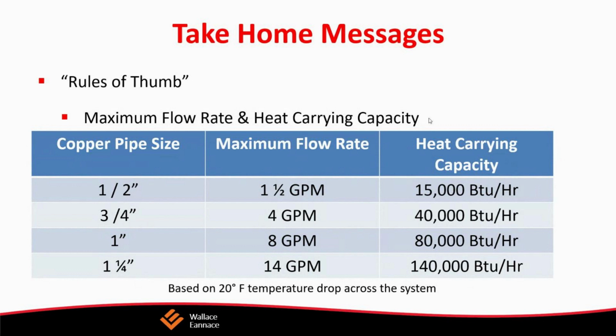So as we start to wind down, we have some really take-home messages. Key things that we want to really focus on here. The first and most important thing is that the net BTU divided by 10,000 gives you the flow rate. So once again, if I have a 250,000 BTU boiler, divided by 10,000 means I'm going to have a flow rate of 25 GPM. If I have a 105,000 BTU boiler, then I'm going to need 10.5 GPM flow rate.